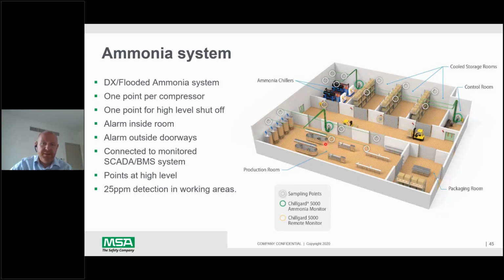So these production areas would need a 25 ppm alarm. And then for the plant room, it would be good to have 25 ppm, then 200 ppm, and then complete shutdown at 30,000 or 40,000 ppm.